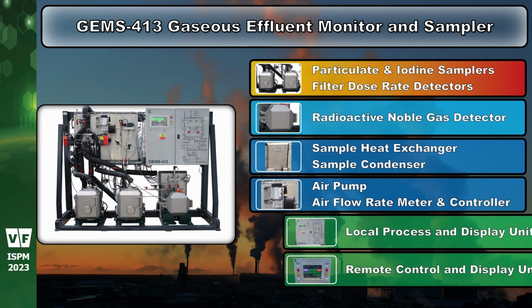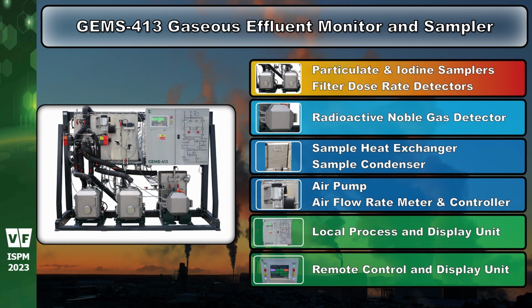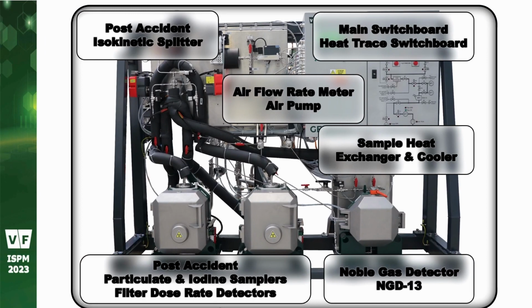The GEMS-413 monitor consists of 2 redundant particulate and iodine samplers with exposed filter dose rate detectors, radioactive noble gas detector, harsh condition sample heat exchanger and condenser, air pump and airflow rate controller, heat traced sample line with thermal insulation and local process and display unit. The remote control and display unit is located in the main control room.